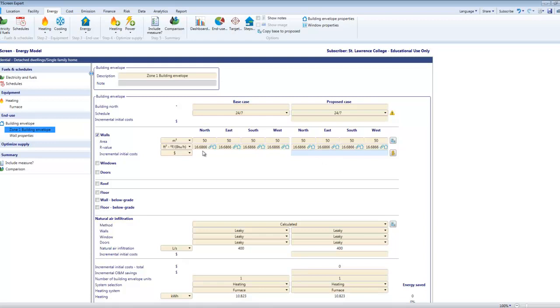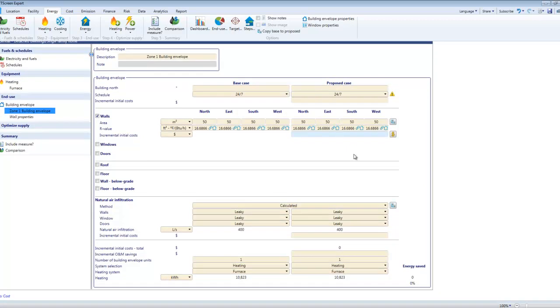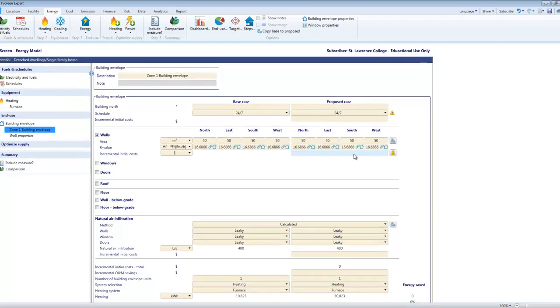Don't change your base case numbers when you're doing upgrade work. If you do that you'll lose track of what they're supposed to be. Always keep your base case intact and make the changes over here in your proposed case. It doesn't matter what you're changing, whether you're doing air leakage, building envelopes, furnaces, keep it all over in proposed case. Make sure that your savings are zero before you start so that you're not carrying some phantom savings in and getting confused.